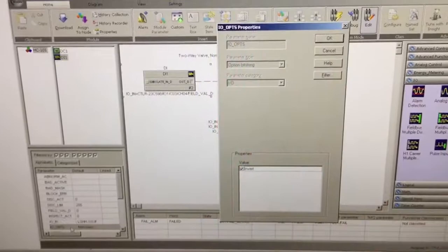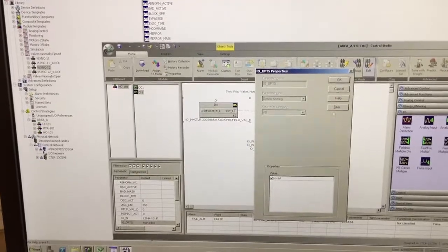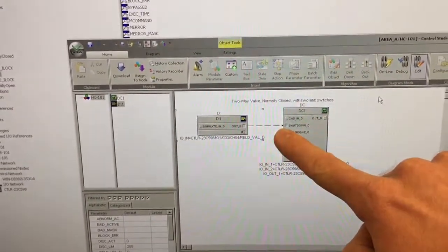You can see this is the level switch tag that we have linked for the actual physical output linked to our system IO in. IO options here, if I double click on it, it gives us the option to invert the signal. So a normally closed switch, which this is, we're representing a normally closed switch, no level, it'd be closed. We want to invert that signal to a 0, because on this DC function block, shutdown coming in, when that becomes a 1, that's what produces that interlock that we were seeing that we had to reset.